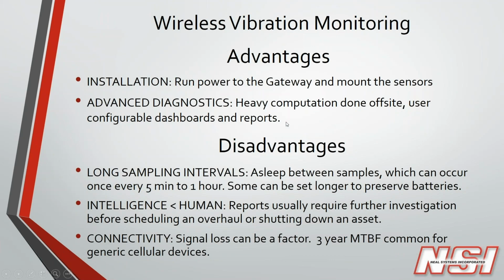But what is wireless? It's essentially portables, but without the expertise, right? And then instead of having a person come around and do your sampling and your reports, you get a bit faster sampling interval. So for advantages, I put installation, right? So you don't have to run conduit, and that's a big cost saver. The advanced diagnostics, I mean, that's huge that you're able to keep the data in its raw form and really get some interesting information out of it. And I put longer sampling intervals here as a disadvantage, because it's important to realize, even though we're sampling every 5 minutes, in some cases, maybe every 1 hour, if you want longer battery life, there's still a lot going on between samples that you're missing.